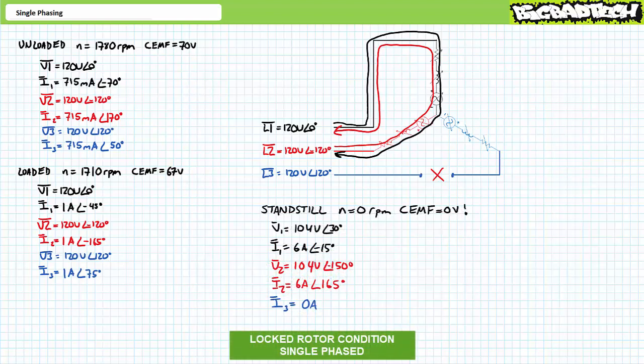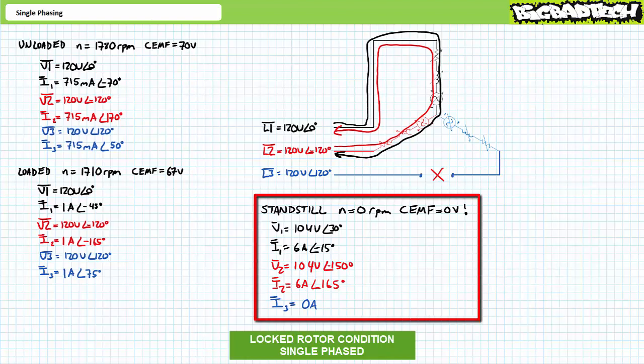Let's now examine the electrical theory behind a single phasing event at standstill for a Y-configured motor — this is where things get really bad. Consider a Y-configured motor at standstill being energized by only two phases: phase L1 and L2 show up on time, while phase L3 is disconnected. Upon closure of the motor starter, the motor would emit an angry buzz and refuse to budge. In the locked rotor condition — i.e., rotational speed equals zero RPM — each winding experiences zero volts of counter-electromotive force in opposition to applied voltage.